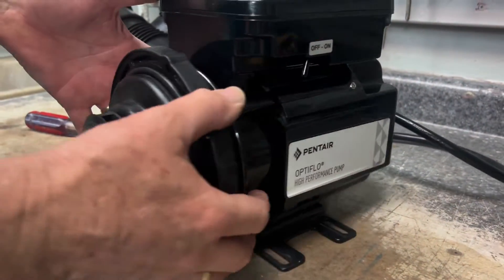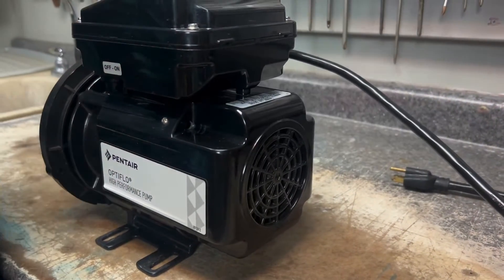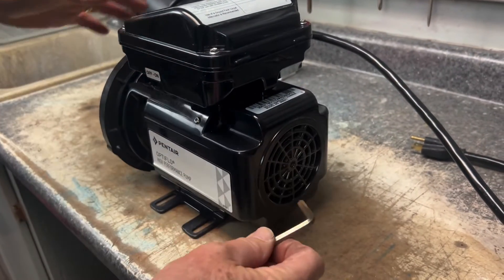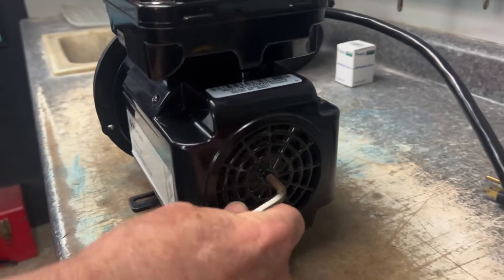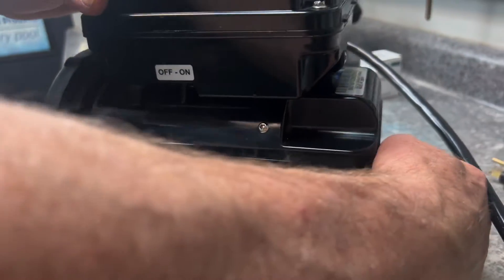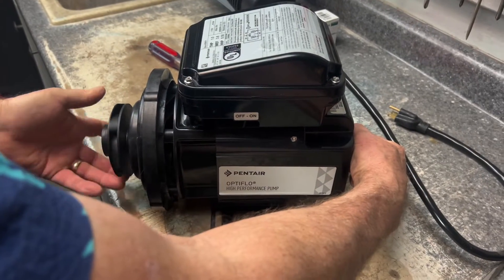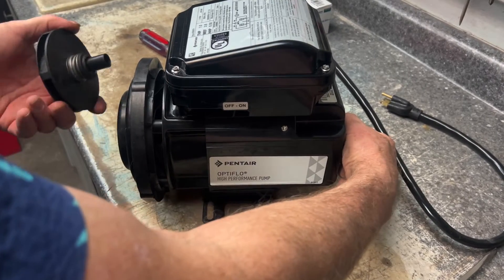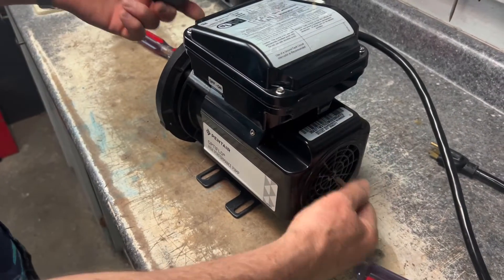Now we're at the front where the impeller is. We're going to turn the motor back this way and get our allen key — this size right here. We're going to stick it in the back and make sure it's locked in, then come around to the front and unscrew the impeller. By holding it back it keeps it from spinning. Now we've got that off.